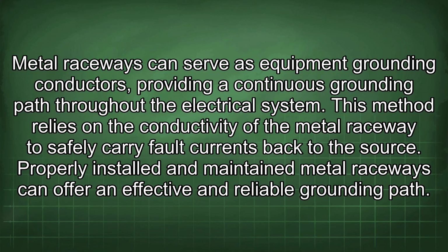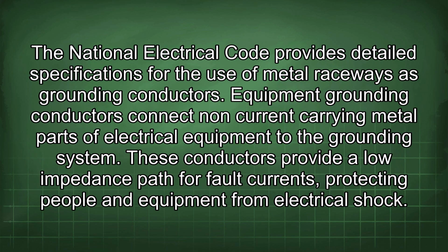Metal raceways can serve as equipment grounding conductors, providing a continuous grounding path throughout the electrical system. This method relies on the conductivity of the metal raceway to safely carry fault currents back to the source. Properly installed and maintained metal raceways can offer an effective and reliable grounding path. The National Electrical Code provides detailed specifications for the use of metal raceways as grounding conductors.